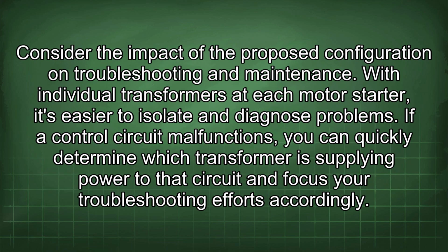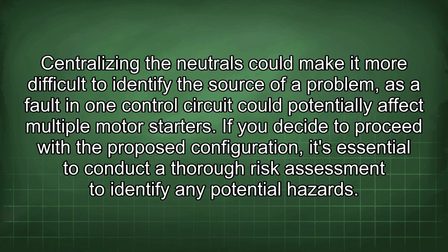Consider the impact of the proposed configuration on troubleshooting and maintenance. With individual transformers at each motor starter, it's easier to isolate and diagnose problems. If a control circuit malfunctions, you can quickly determine which transformer is supplying power to that circuit and focus your troubleshooting efforts accordingly. Centralizing the neutrals could make it more difficult to identify the source of a problem, as a fault in one control circuit could potentially affect multiple motor starters.